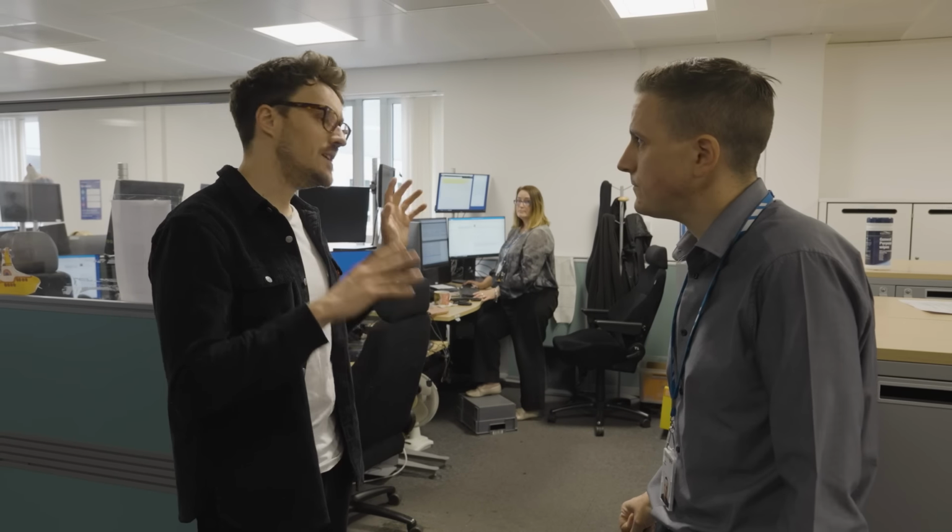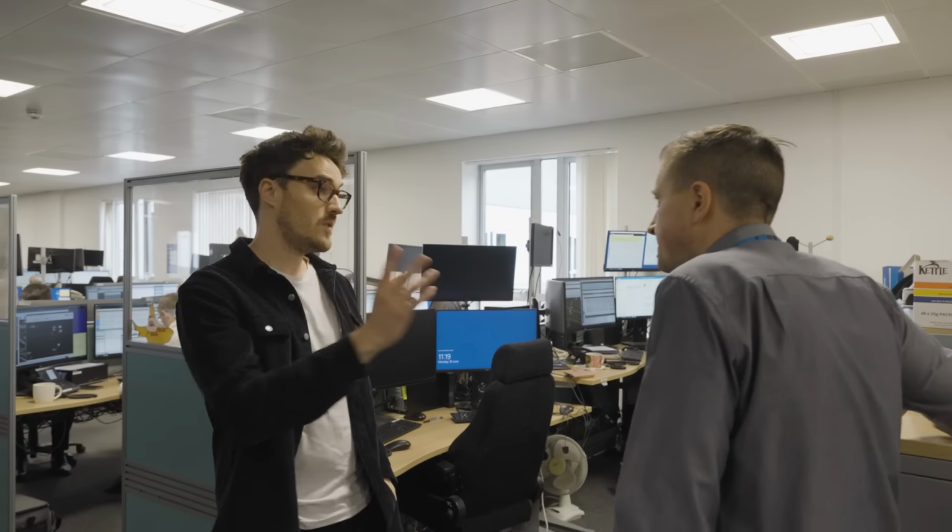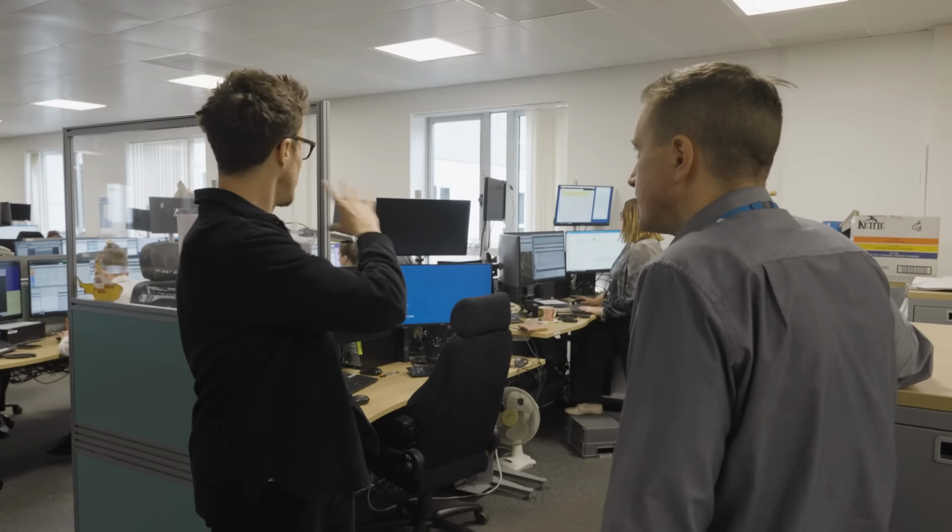How often do you need to actually send physically a team out or actually dispatch someone to a property or to a line? Is that quite common? In the Midlands, for example, we're handling around 300 incidents a day. Wow. So that varies from defects that a meter operator might have gone out on site and found, and we have to go out and do a small repair, to smaller low voltage faults, 10, 30, 40 customers, and then we've got the high voltage network, so we might be in the thousands there, so it all varies from incident to incident.